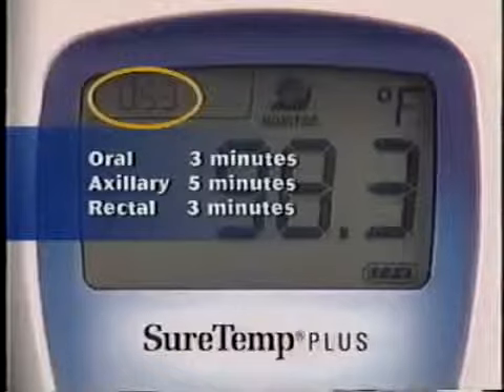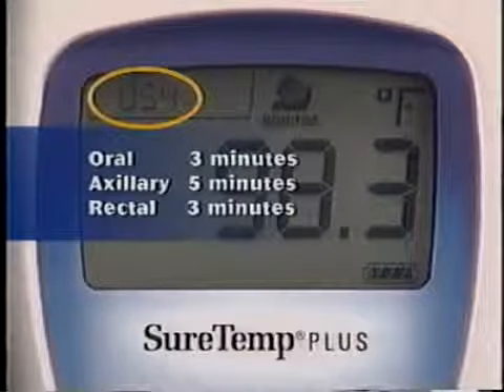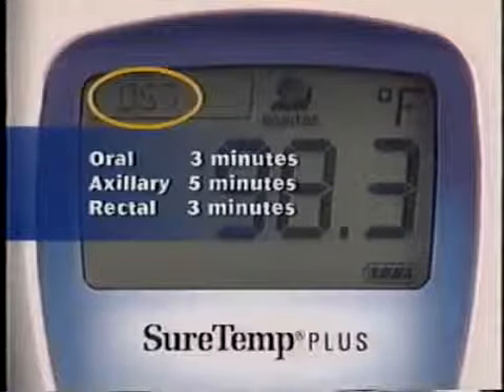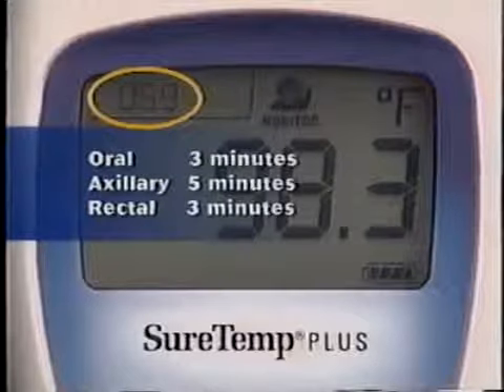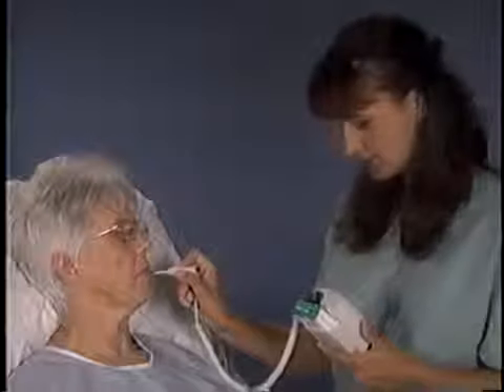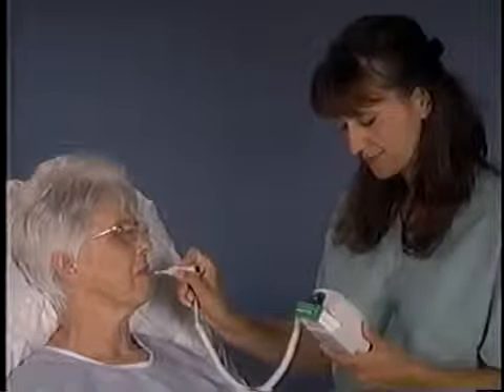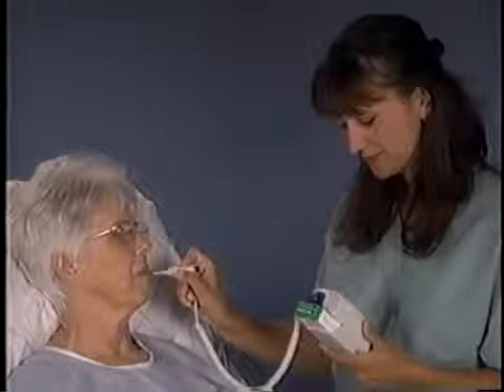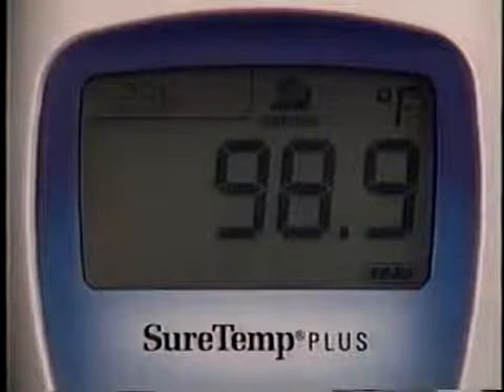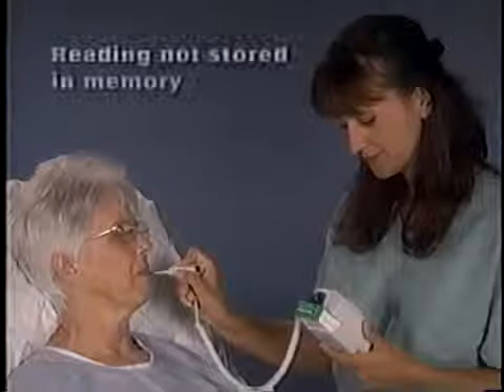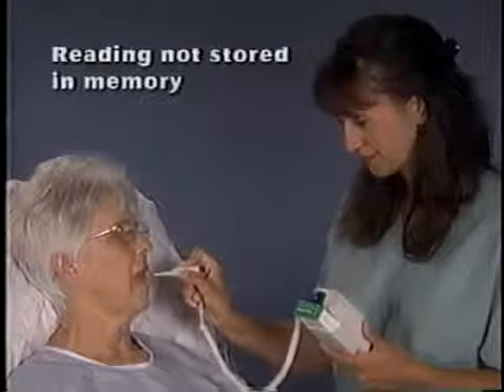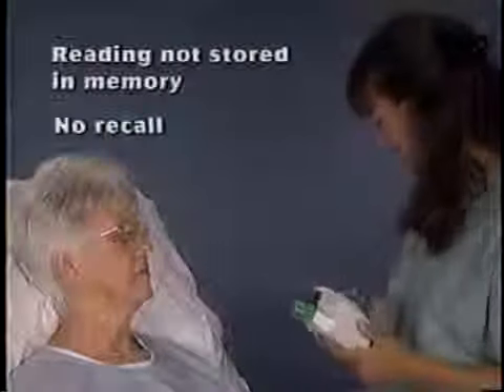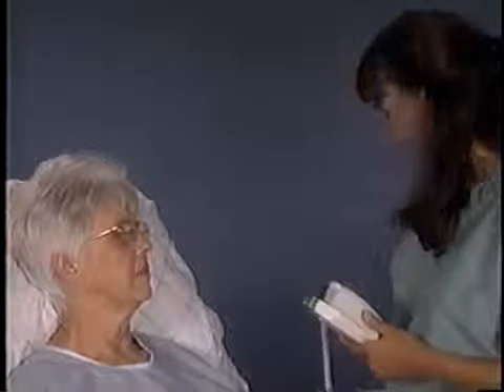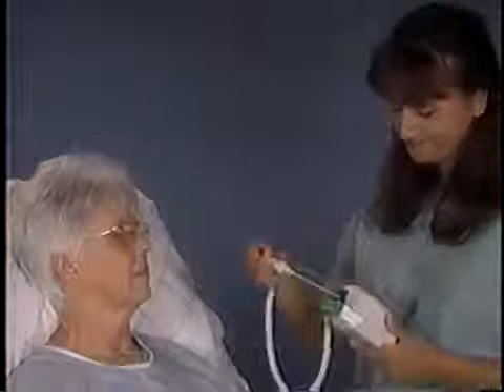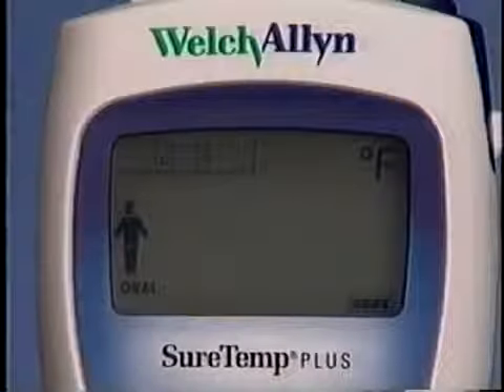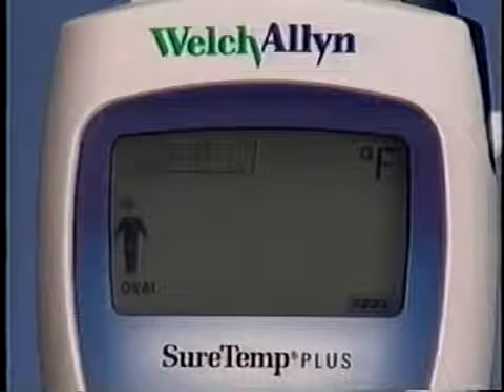Use the timer in the upper left of the screen to time the monitor mode measurement. The thermometer will not beep to indicate a final temperature. It is important to note the temperature before removing the probe from the patient's site and ejecting the probe cover. The temperature reading for a monitor mode measurement is not maintained in memory and cannot be recalled with the recall button. Once the probe is placed back in the well, the instrument will return to predictive mode.